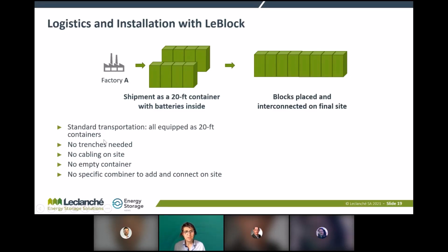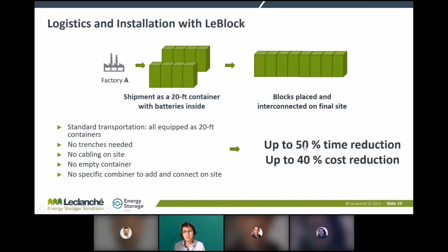You don't need trenches, you don't have to do cabling on site, you don't have an empty container to send back, and there's no specific combiner with DC protection to add and connect on site. We've run simulations on different projects and concluded that we're able to reduce installation time by up to 50%, and in some projects achieve up to 40% cost reduction for transportation and installation. So it's a really big improvement.